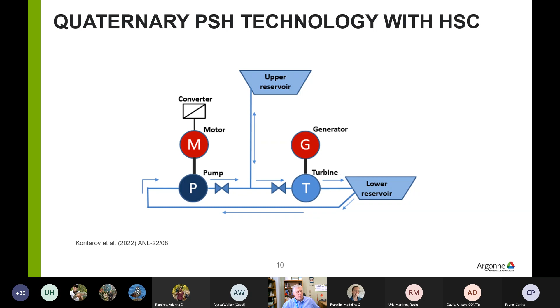So how does pump storage support the grid? We know that clean energy goals require reliance on large amounts of variable energy resources like wind and solar, but because of their variability, those are sometimes difficult to manage. Pump storage enables high penetration of these resources in the system because it provides large quantities of energy storage and the full range of ancillary services that are necessary for grid operation. Also, pump storage provides a large amount of flexible dispatchable capacity. With hundreds and thousands of megawatts, pump storage can always serve to cover the shortfalls in wind or solar generation. It can also mitigate overgeneration of wind and solar through time shifting and storing excess generation for later use.